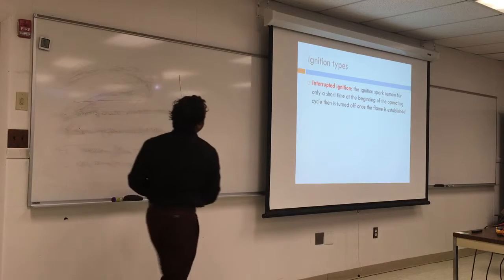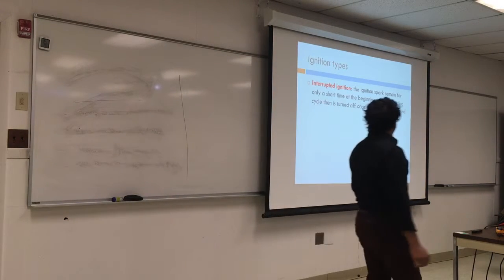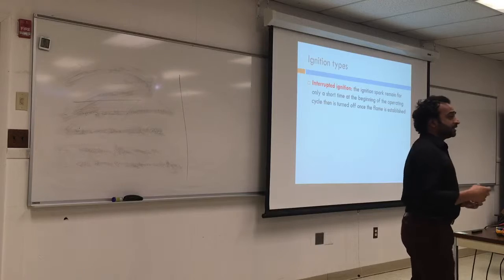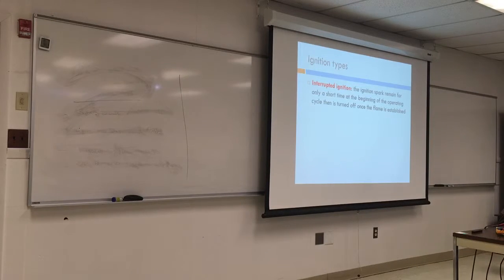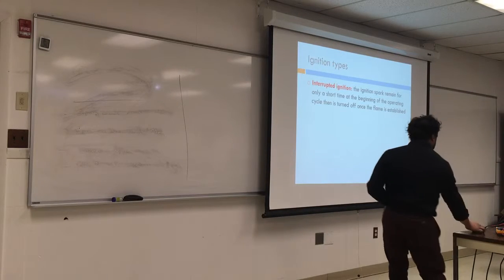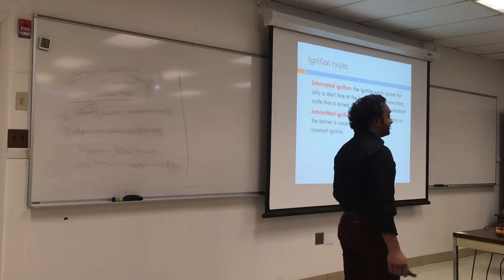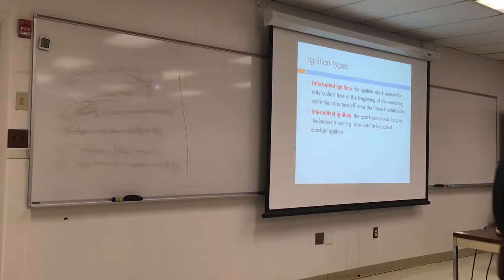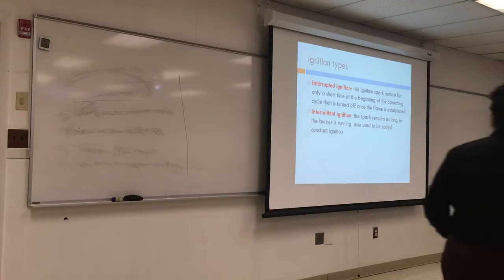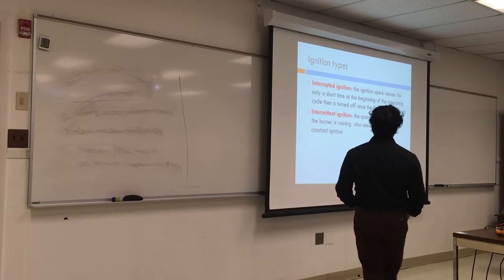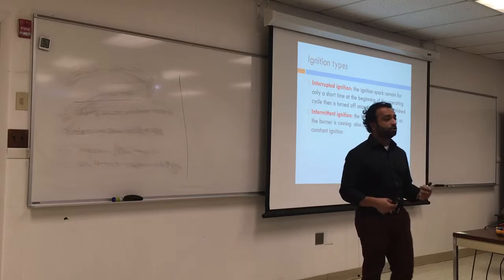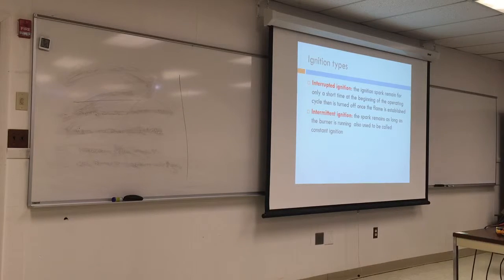So this is kind of confusing. The first thing is called interrupted ignition, which means the ignition comes on until the flame is on, then it goes off. That's interrupted ignition. And there is a second thing, which is intermittent ignition, which, if you think about it, also means it will stop, right? It's not continuous, but for some reason, it also means continuous. So the spark will continue to light up through the entire cycle.